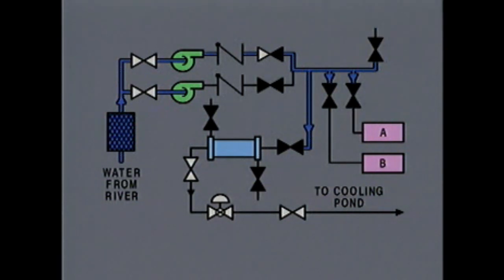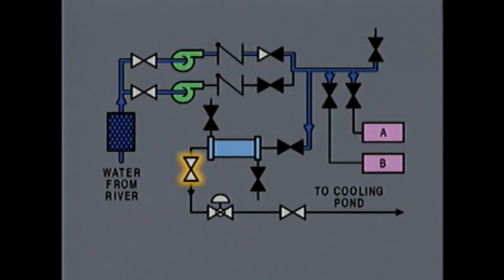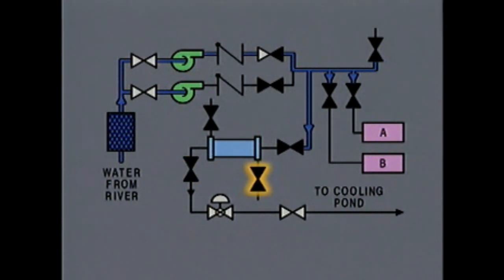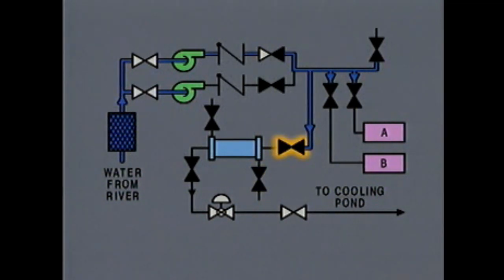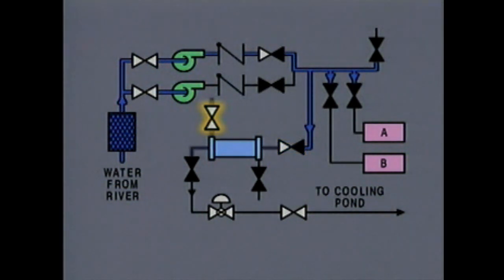Now the next step is to supply water to the lube oil cooler. First, the isolation valve in the oil cooler tube side outlet line is closed, and the tube side drain valve is checked to make sure it's closed. Then the tube side of the cooler can be filled by partially opening the inlet isolation valve and completely opening the vent valve. When water has completely filled the cooler, the vent valve is closed.